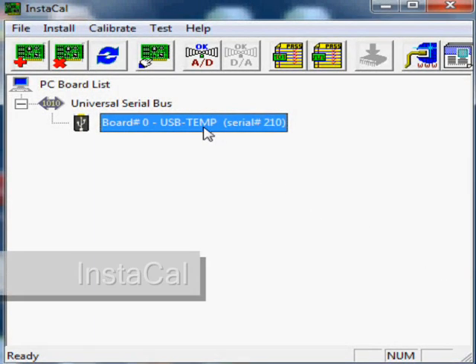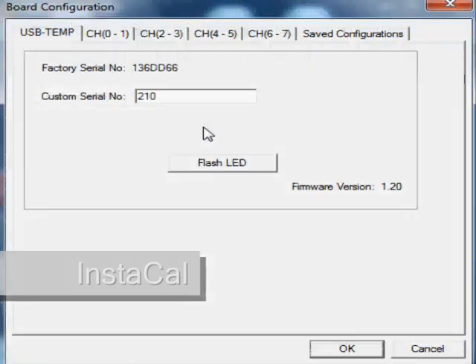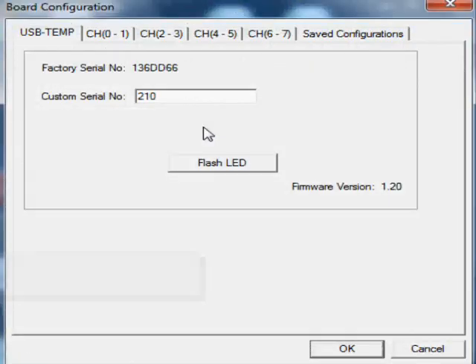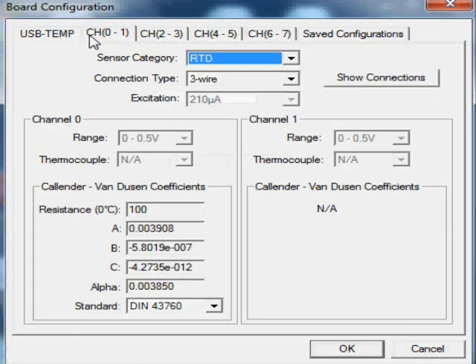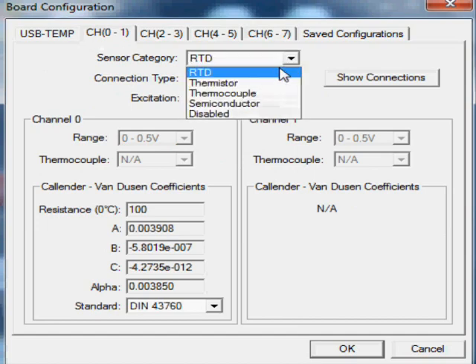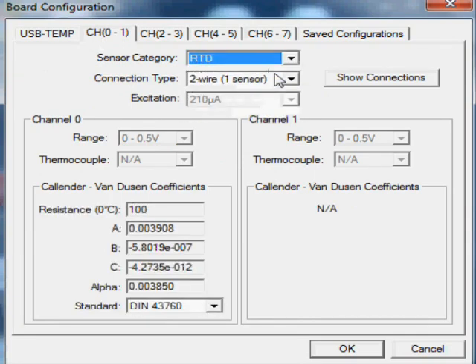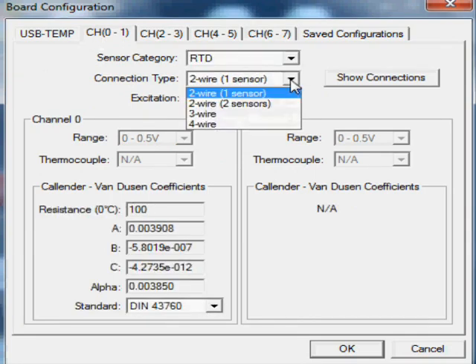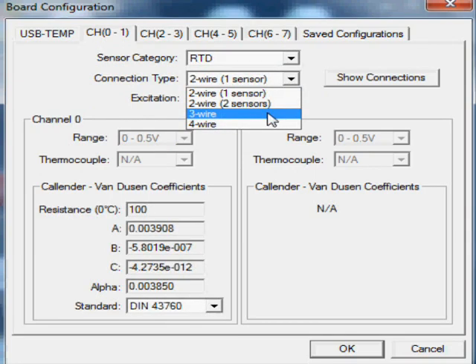Next, we configure the module using the included Instacal application. We select the sensor type here. Instacal also provides a wiring guide for connecting our RTD.